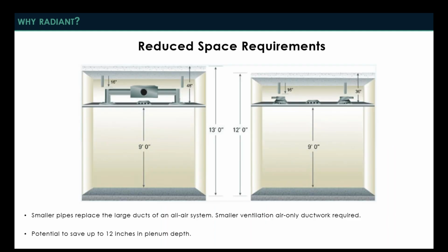The other major benefit of a 1-inch pipe versus a 16 by 16 duct is reduced space requirements. And this is something that architects I've worked with have wanted to adapt this technology for. This is sometimes one of the prime movers, that they're trying to reduce the amount of space in the plenum that the HVAC system takes up so that they can either reduce the floor-to-floor height for each floor of the building, or to maximize their ceiling heights, or both.